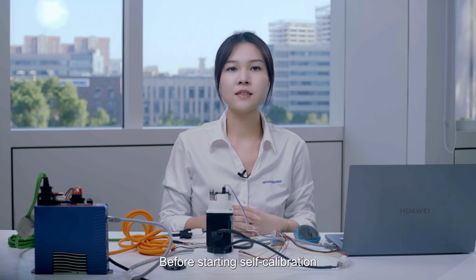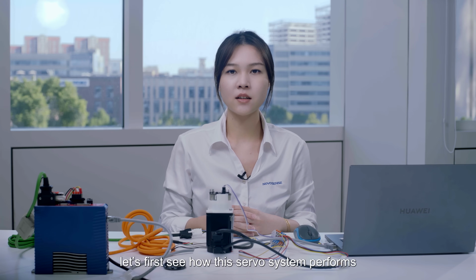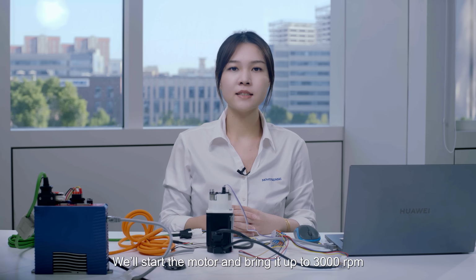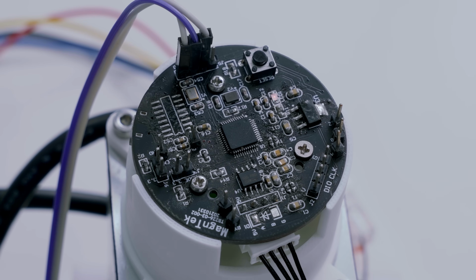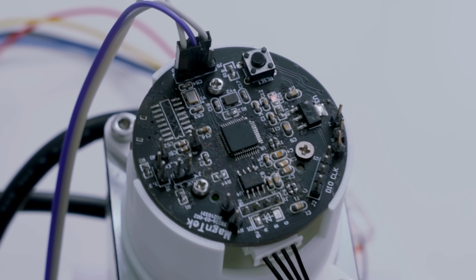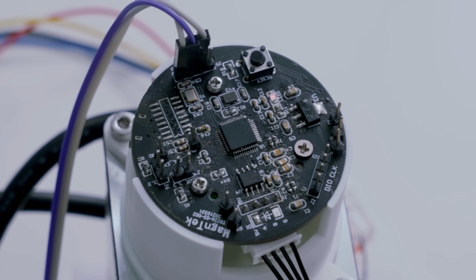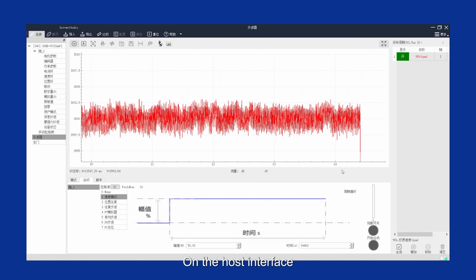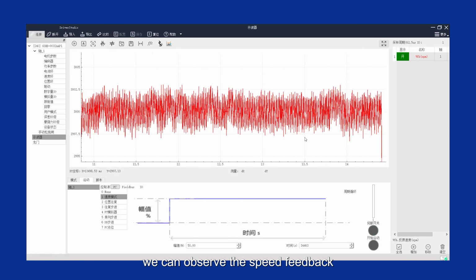Before starting self-calibration, let's first see how the servo system performs with the optical encoder. We'll start the motor and bring it up to 3000 revolutions per minute. On the host interface, we can observe the speed feedback from the optical encoder. At 3000 revolutions per minute, the speed fluctuation is around plus or minus 2.5 revolutions per minute. We'll use this as our reference data.